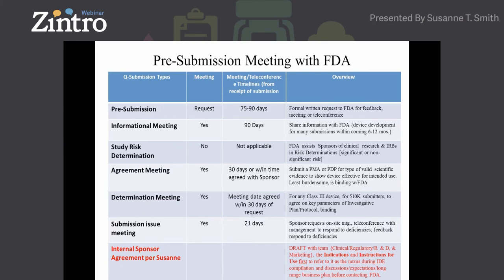I created a table showing the different types of pre-submission meetings you can have with FDA regarding an IDE, and how long they take — it can be months; you may not be able to meet FDA for six months. One strong suggestion I've learned over the years, shown in red at the bottom: draft your instructions for use and your indications first. Get it down in writing and get your team together — clinical and regulatory people, R&D, marketing, all who will influence the product description, labeling, and promotion. It will keep everyone on the same path, speaking the same language, with the same expectations.